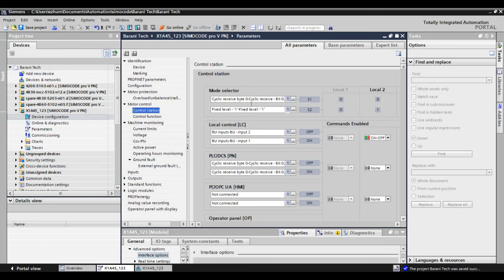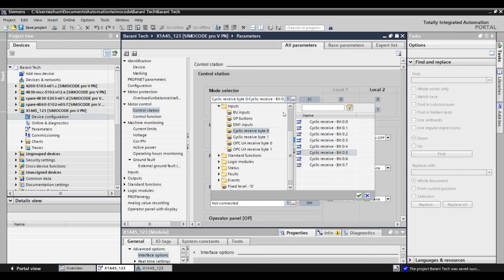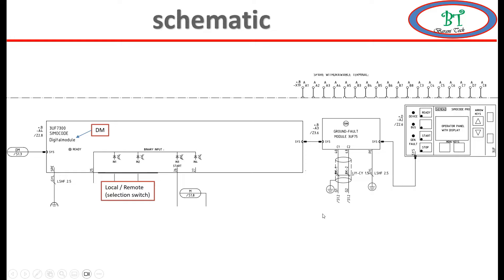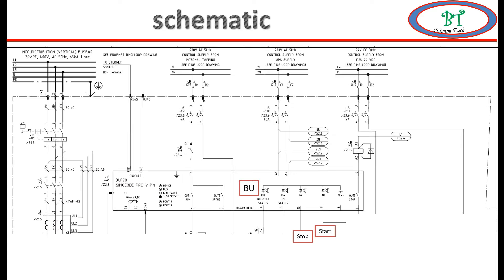By this we came to the end of protection settings. Now we go for motor control. First we will see the motor control station — this is very important to understand for on/off module. In mode selector, we have S1 and S2. Activating S1 and S2 can be done by binary input or soft input from the remote end. I am going to explain using binary input. Let us consider S1 is configured by DM1 Input 1 and S2 is DM1 Input 2 as per the schematic diagram. For local start, I am going to configure BU Input 2 for stop signal and BU Input 1 for start signal.